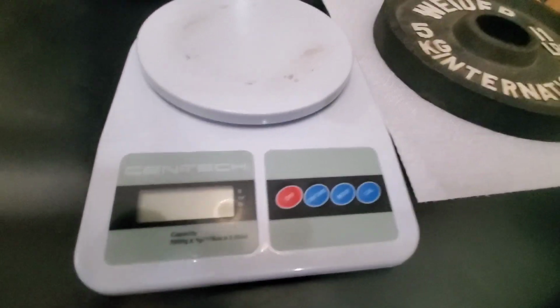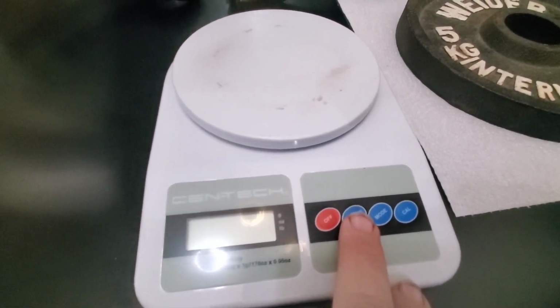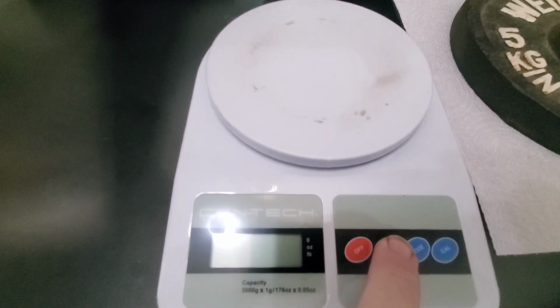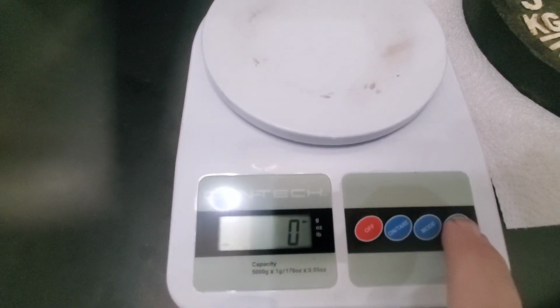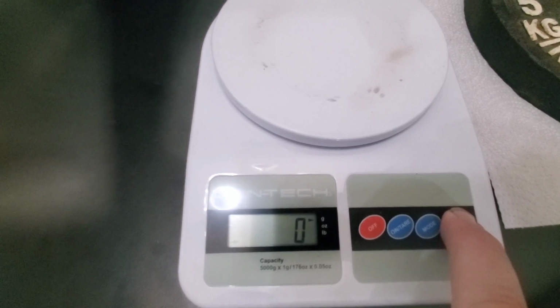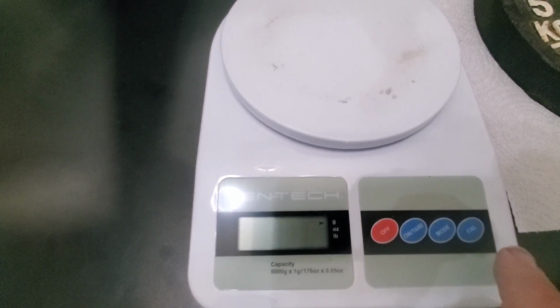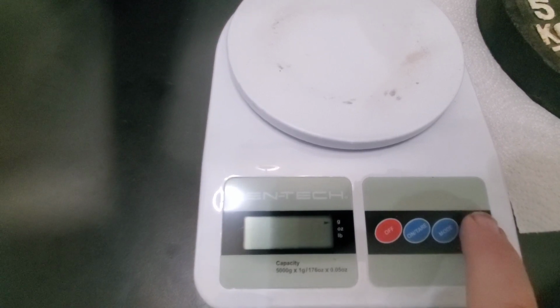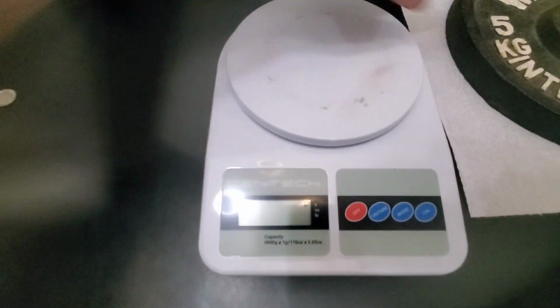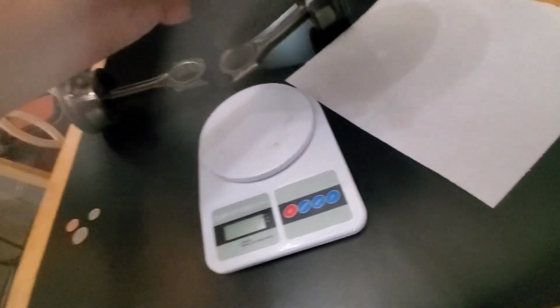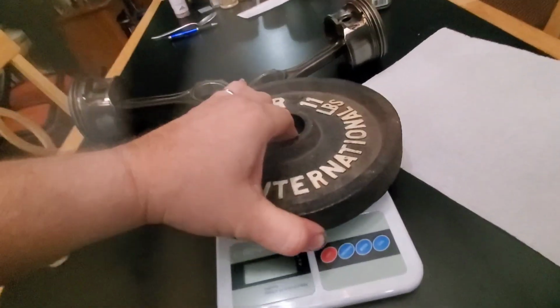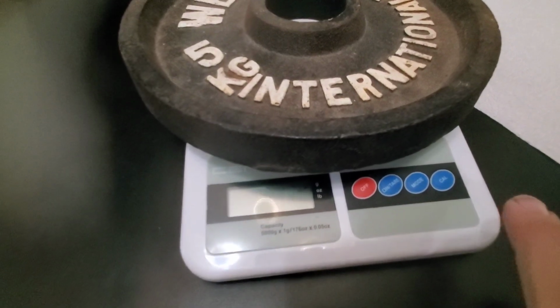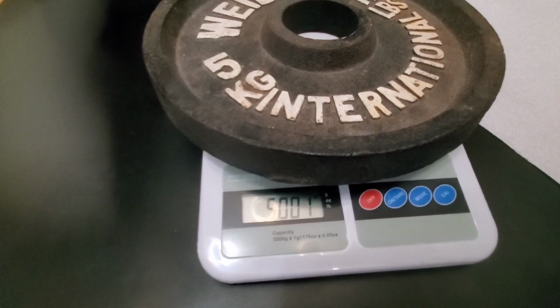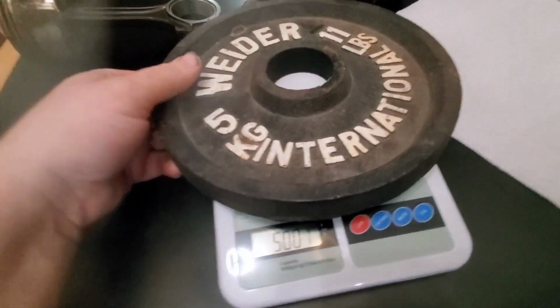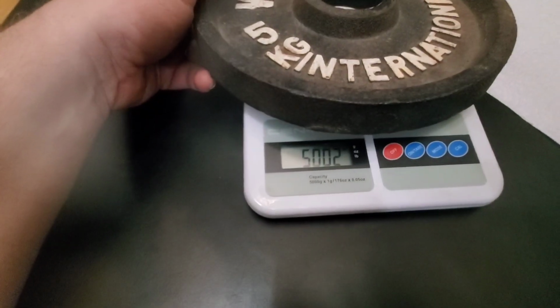So what you do is, I'm going to have to do it twice. I'm going off memory, but you turn it on. You hold calibration down for 3 seconds until it says calibrate, and then when it's flashing, press calibration again. 5,000. So it's asking you to put 5,000 grams, which is 11 pounds, on the scale. Then you set 11 pounds on the scale. Calibration again, pass. All right. So now, once you've done that, you're calibrated.